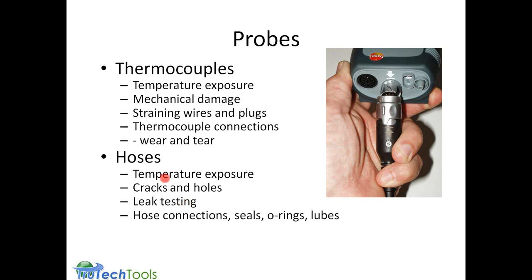Hoses: overexposure and temperature, cracks or holes or leaks. These, again, are for any type of combustion analyzer. There's really not too much to worry about in the 327 because of the single hose assembly with the really tough over casing. It's almost impossible without using a Sawzall to get a crack or leak in a 327 hose.